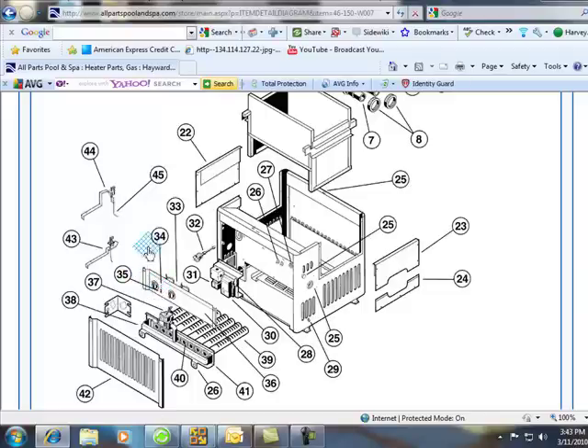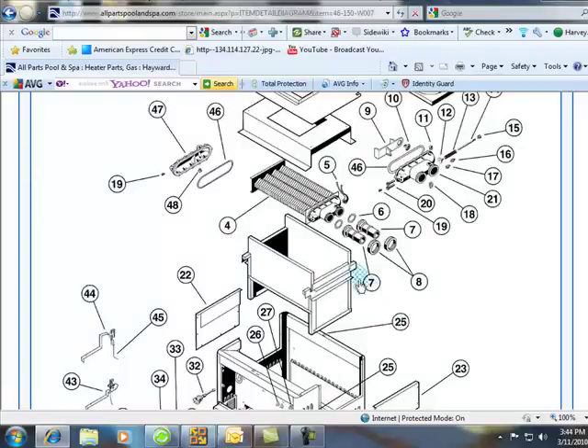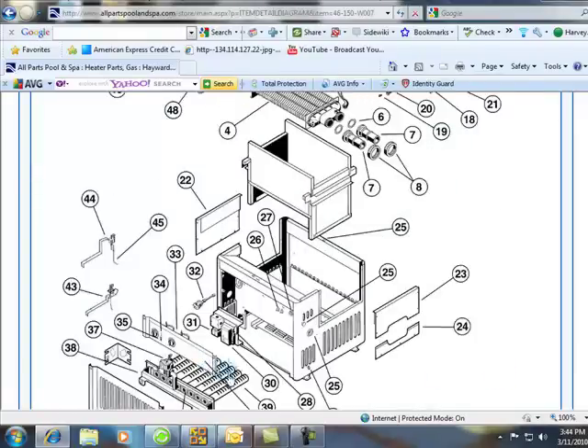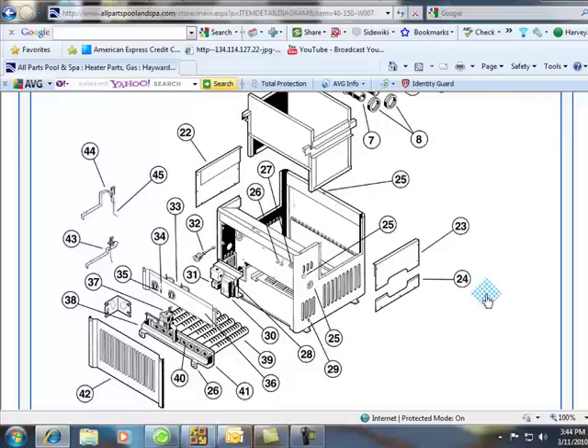Next one might be this little sensor right here, 26. And it's a rollout sensor. Never bypass them. When I was out in the field, I always saw them bypassed. It is a safety system. When this heat exchanger possibly starts sooting up or clogging or deforming, and it can't do the proper venting...